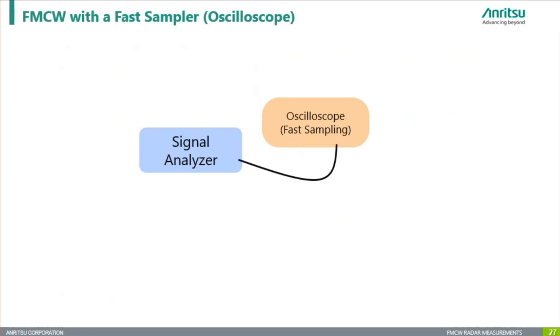This data is then broken down and analyzed to extract the key parameters, such as chirp slope, frequency, linearity, and other critical characteristics. This method enables a comprehensive analysis of the radar signal and is considered an excellent solution for in-depth RF evaluation.